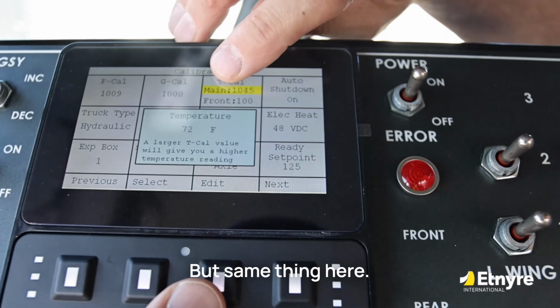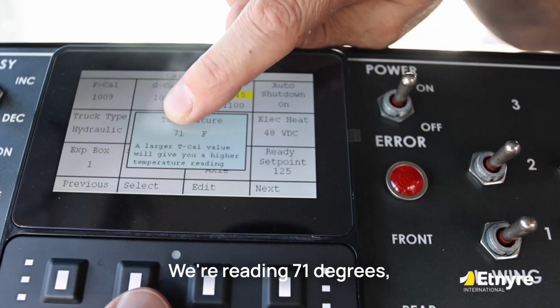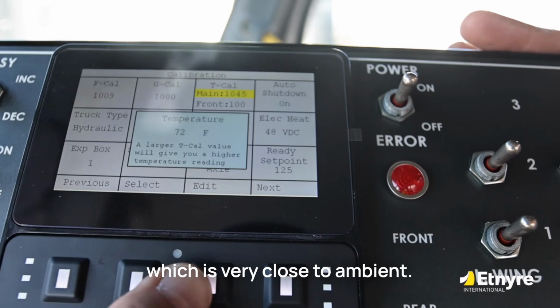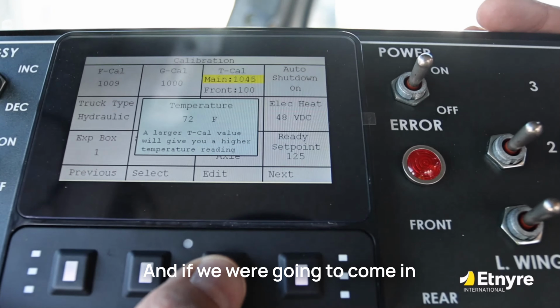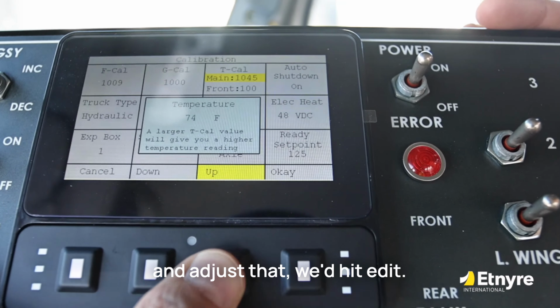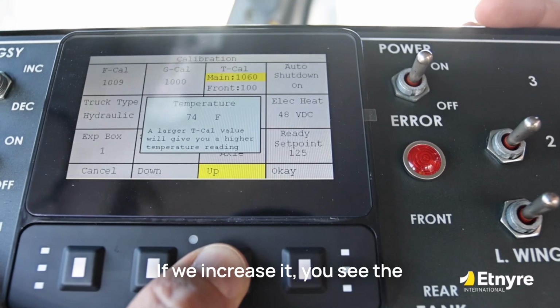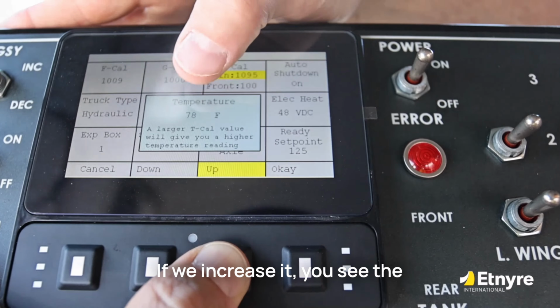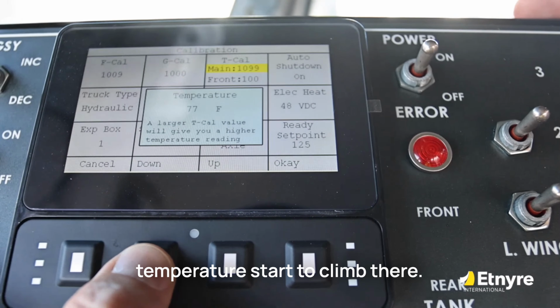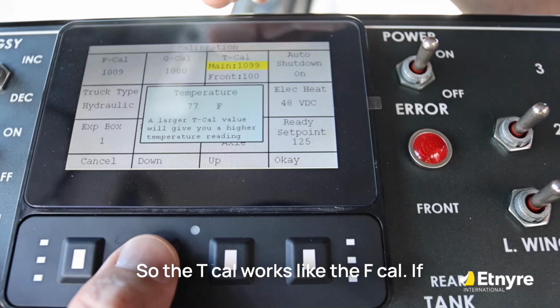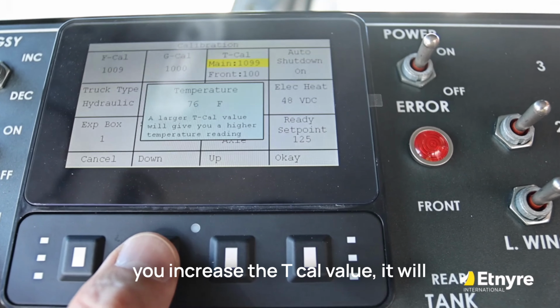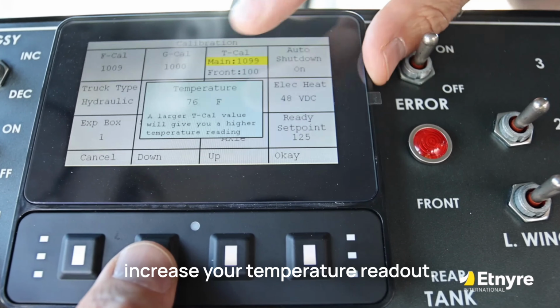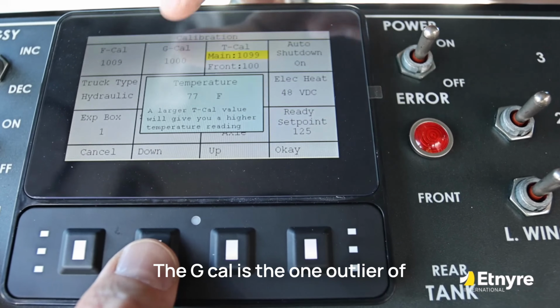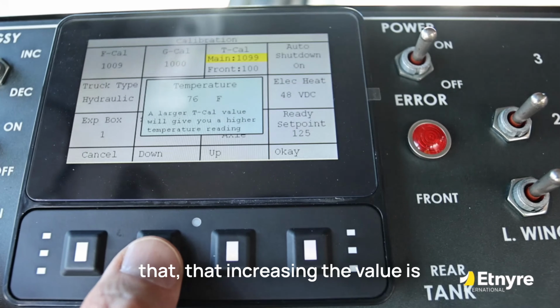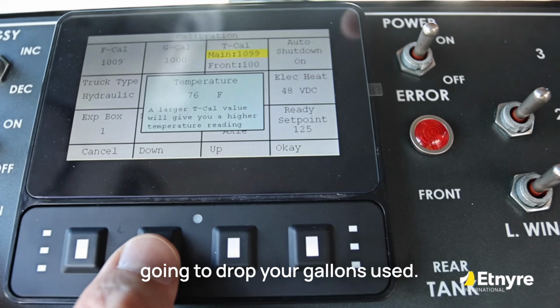But same thing here, you can see it's at 1045, we're reading 71 degrees, which is very close to ambient. And if we were going to come in and adjust that, we'd hit edit. If we increase it, you see the temperature start to climb there. So the TCal works like the FCal. If you increase the TCal value, it will increase your temperature readout. The GCal is the one outlier, where increasing the value is going to drop your gallons used.